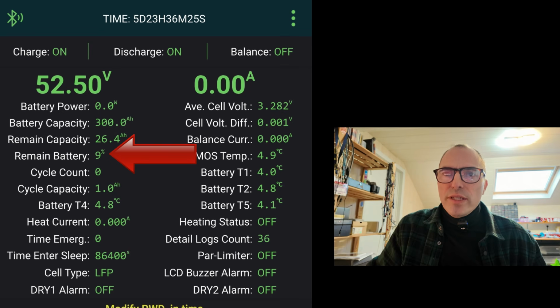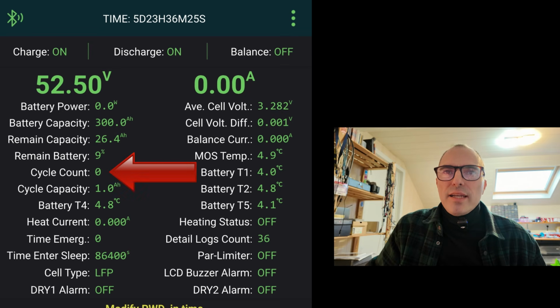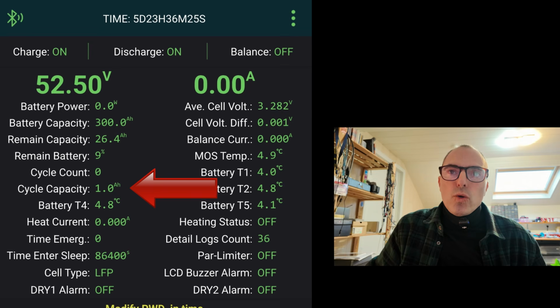Remain battery is a calculated percentage of the remaining capacity, also known as SOC or state of charge. Like above, a full cycle is needed to determine the correct state of charge. Cycle count is measured by the energy or coulomb meter. For every 300 amp hour of energy in or out of the battery, the counter is increased by 1. The cycle capacity is the cumulative sum of energy that went in and out of the battery. Over the years, this number will grow to 5 or 6 digits.